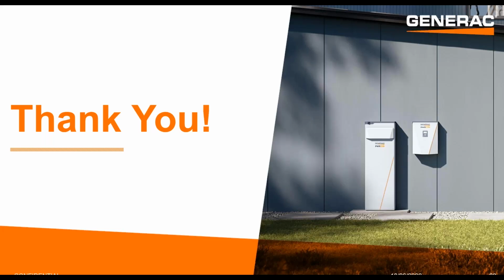When we're DC coupled, yes, it switches automatically. In gen integration, we'll power the house from solar first, then kick in the battery if needed. If solar and battery can't cover the load, or if the battery hits too low a state of charge, the generator automatically kicks on, takes over the house load, and recharges the battery simultaneously. That is seamless. I have this set up at my own house and I've seen it work.